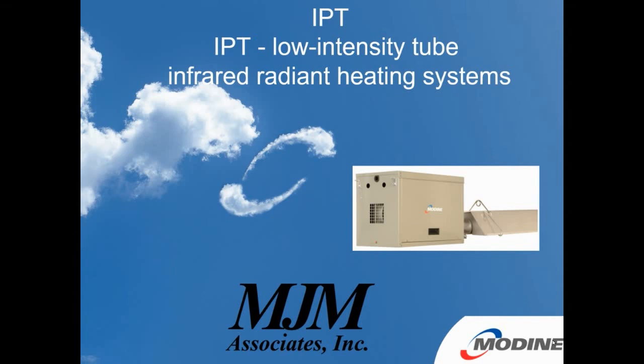And remember, with radiant infrared heat, you're heating objects. You're heating a mass. You're not heating the air. You could go into an infrared system and the floor will be 65, 70 degrees, but it'll be 50 degrees in the room because of the fact you're heating the mass.